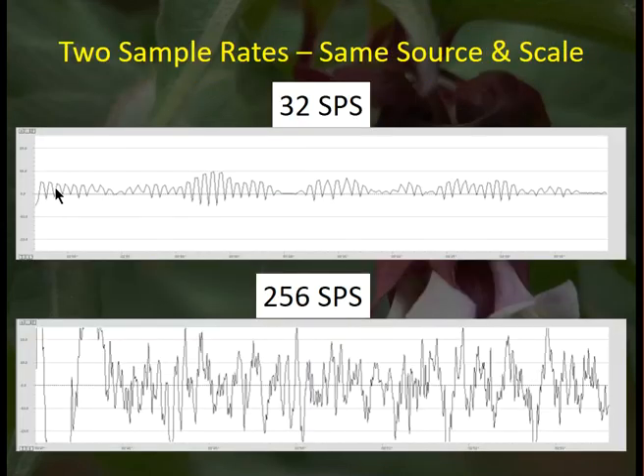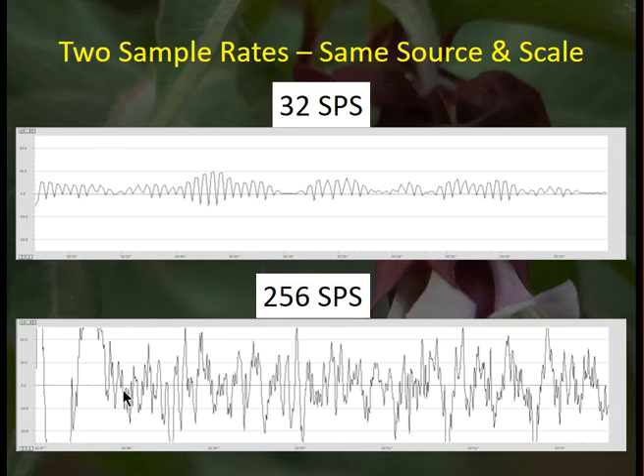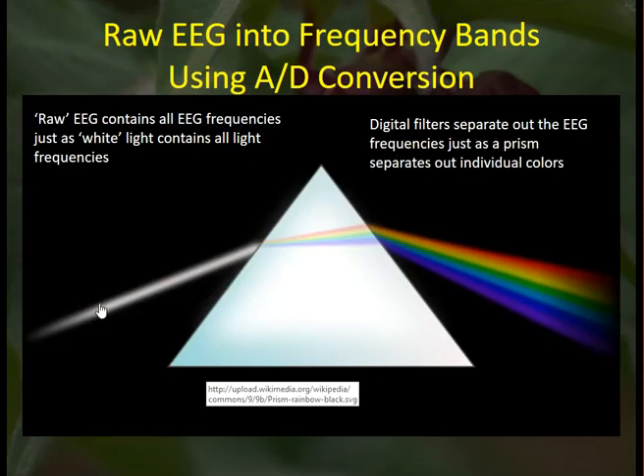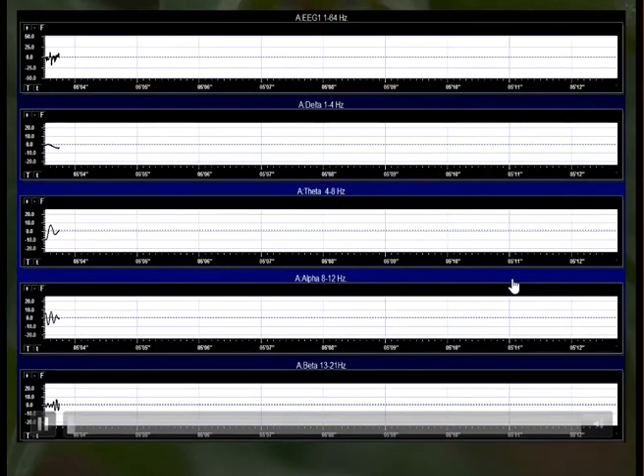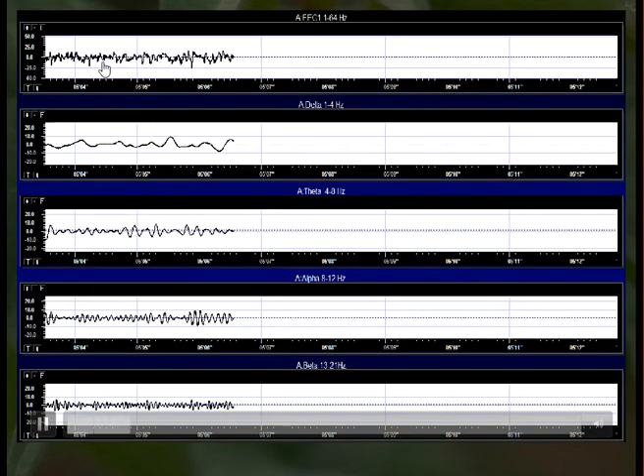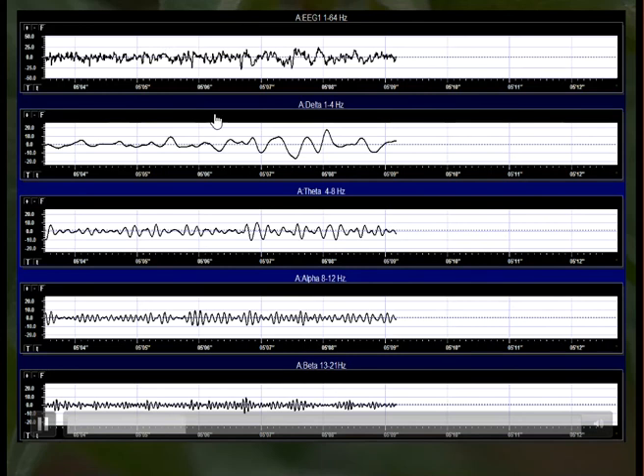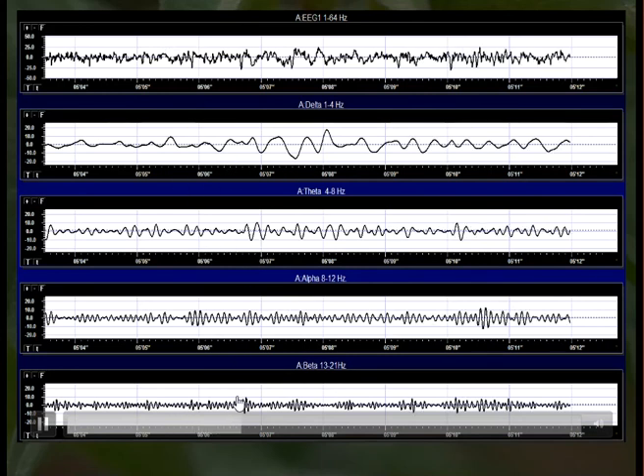Here we have two sample rates from the same source: the incoming EEG signal sampled at 32 samples per second lacks a great deal of information compared to the same signal sampled at 256 samples per second, which provides excellent resolution and detail. Just as shining white light through a prism breaks it into different frequencies of light, we do the same with our EEG — bringing in the raw signal and breaking it down into different frequency bands using band-pass filters.